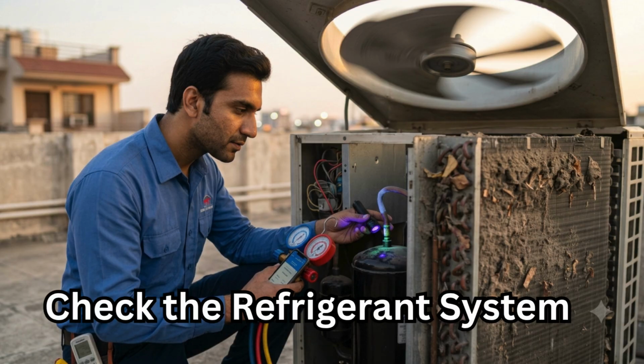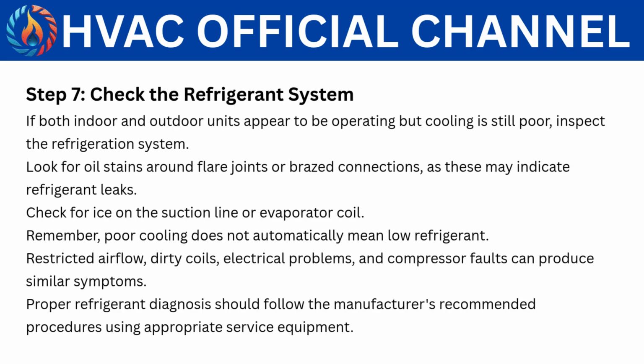Step 7. Check the refrigerant system. If both indoor and outdoor units appear to be operating, but cooling is still poor, inspect the refrigeration system. Look for oil stains around flare joints or brazed connections, as these may indicate refrigerant leaks.